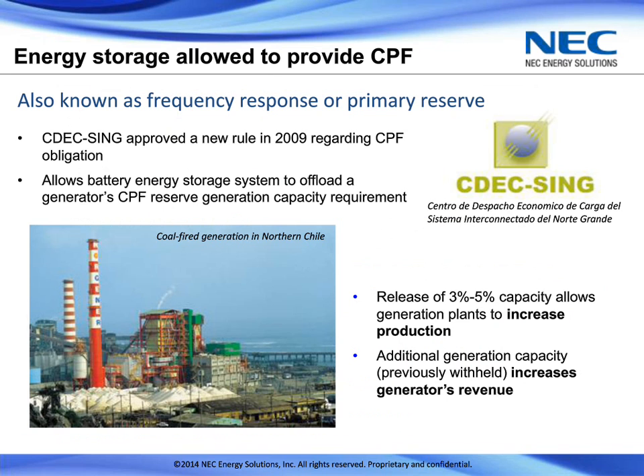So as we look again into this particular case study in Northern Chile, a few things have happened to allow energy storage to provide CPF. CPF again is primary frequency control. That's the acronym they use down there to represent that service. So back in 2009, a new rule was approved by CDEC-SING, which is the authority down there, regarding who or what can provide CPF. That rule allowed battery energy storage systems to offload a generator's CPF reserve generation capacity requirement.